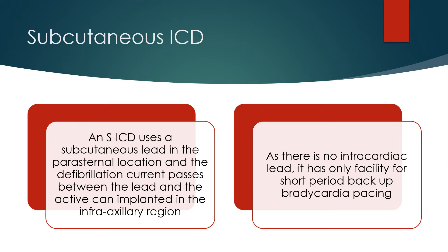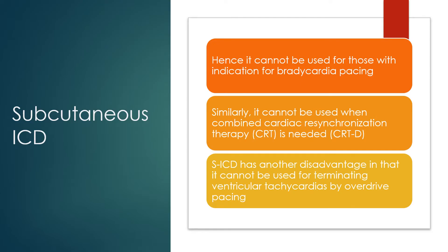As there is no intracardiac lead, it has only facility for short period backup bradycardia pacing. Hence, it cannot be used for those with indication for bradycardia pacing. Similarly, it cannot be used when combined cardiac resynchronization therapy is needed. SICD has another disadvantage in that it cannot be used for terminating ventricular tachycardias by overdrive pacing.